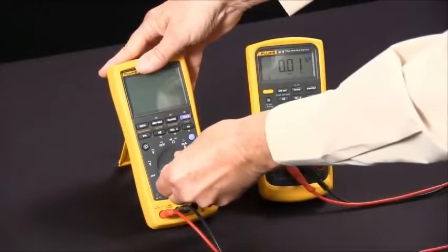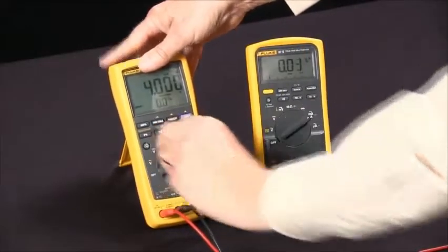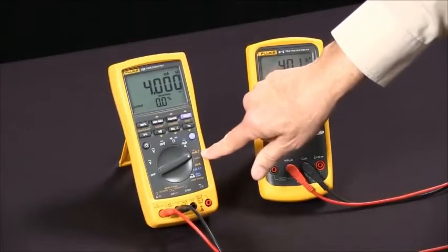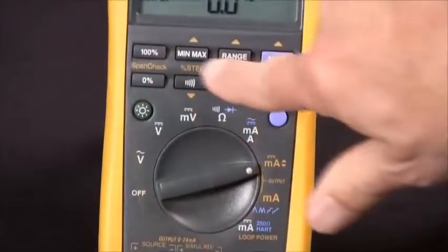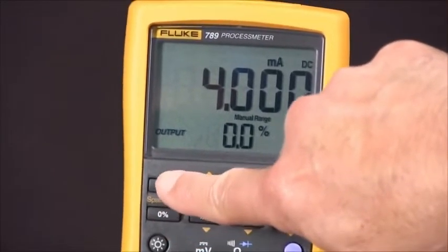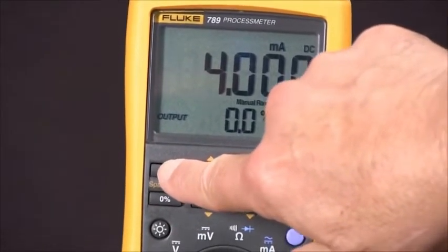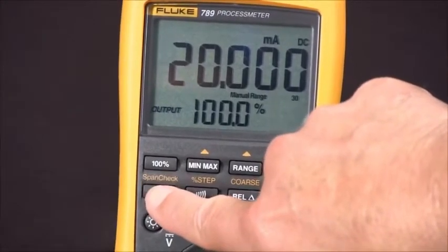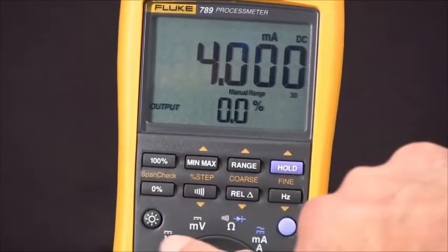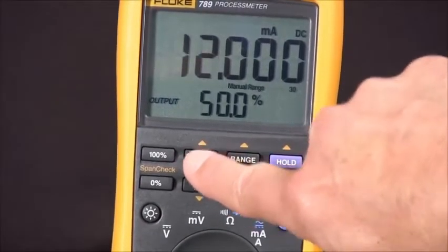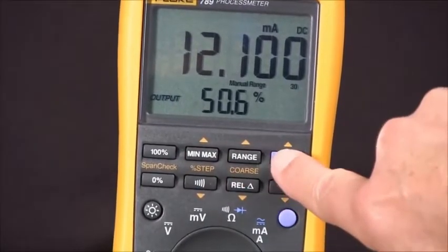We'll rotate the rotary knob to the DC milliamp position. From here we have several choices to control it. We can start with the span check and go from 0% of span to 20 milliamps or 100% of span or zero. Then with these three we can do 25% of span coarse or fine adjustments.